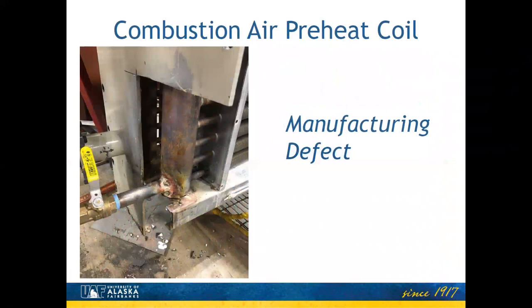The boiler draws in a lot of outside air for combustion, and Babcock and Wilcox provided us this combustion air preheat coil by a manufacturer that they used dozens of times. But somebody was having a bad day at that factory when they put that solder joint together, because it was leaking pretty substantially, so we had to get that repaired.